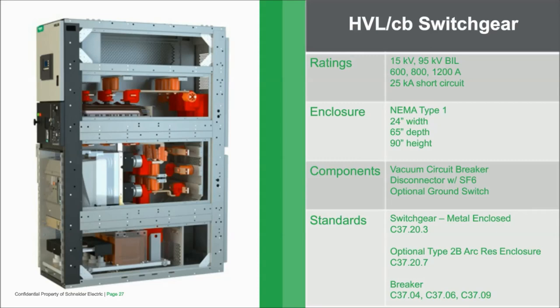Is there a set number of times the disconnect can be operated before it needs repair or replacement? The life of the disconnect is dependent on the actual amperage sent to it. As the conductors rotate and the copper ends take some abuse from operation, the damage depends entirely on the amperage of that break. We have graphs and charts demonstrating that the more operations and the higher the amperage, the shorter the life. At 600 amps, we see something closer to a thousand operations.